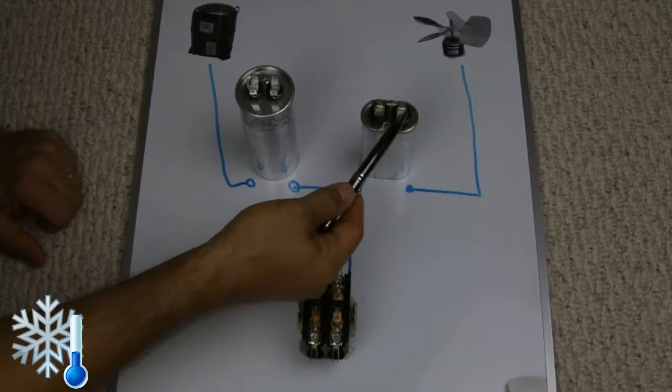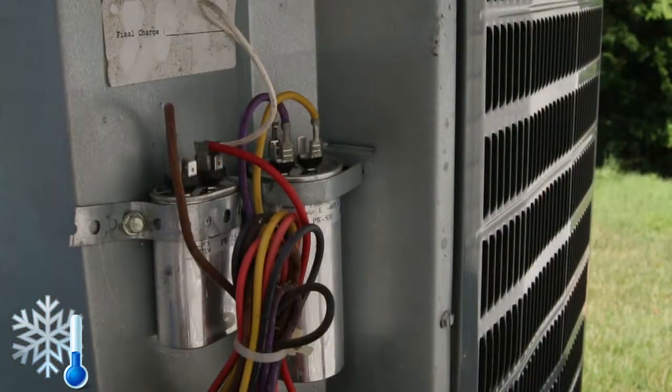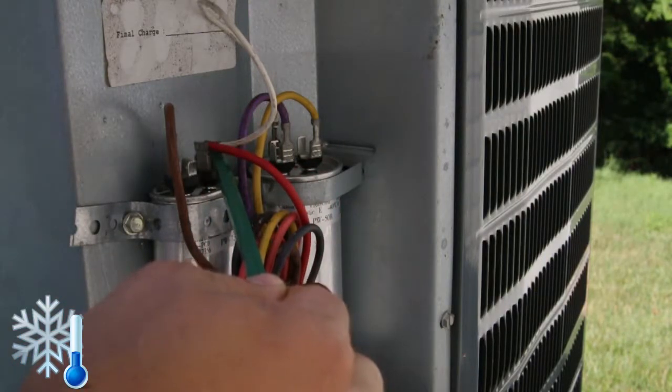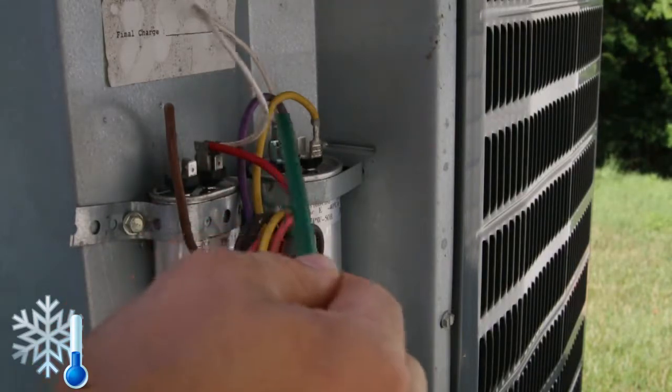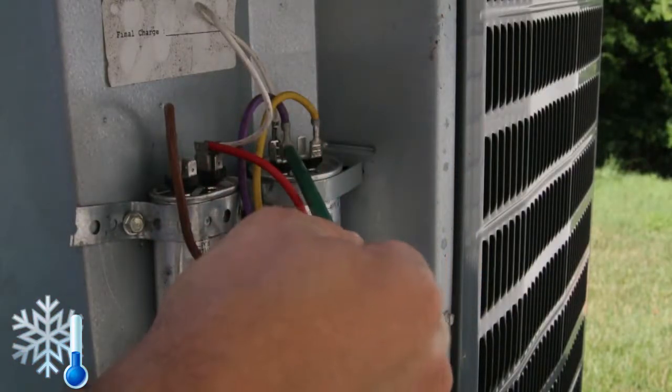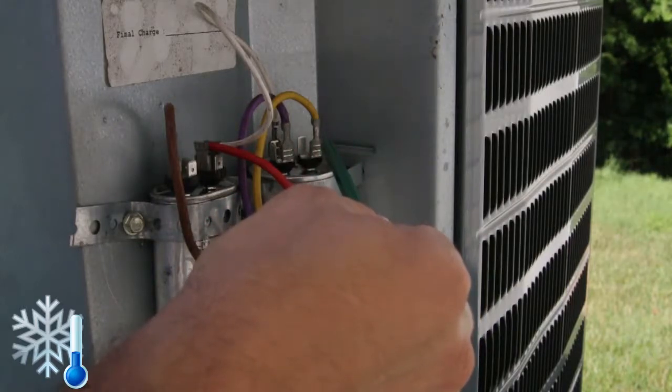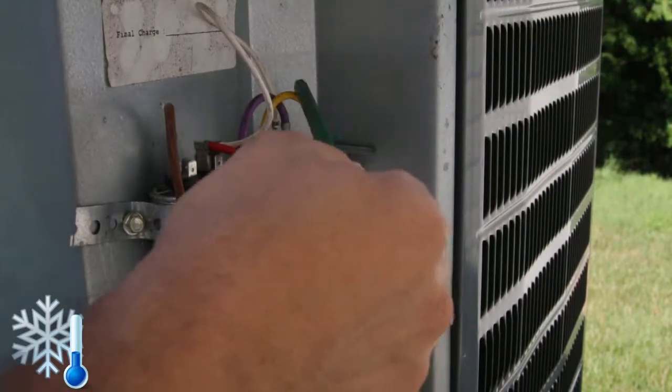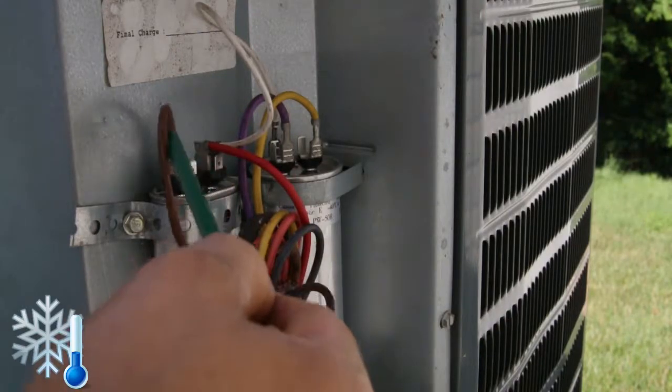The common wire coming from the contactor goes to one side of one capacitor. Then we got a jumper wire, the white wire is actually jumping so that one is common side too. From the other side of the compressor capacitor, the wire is connected toward the compressor, and from the other side of the fan capacitor it's connecting the fan.